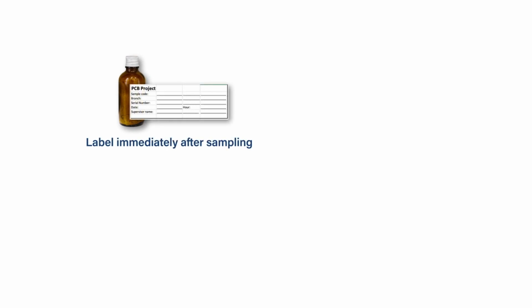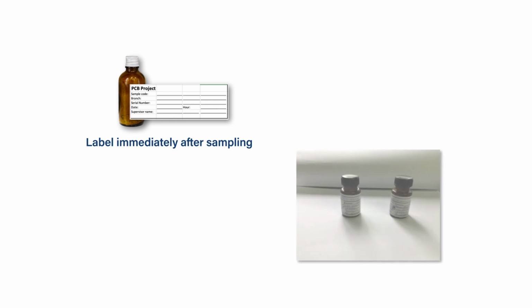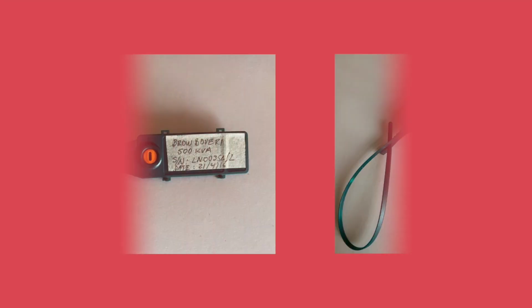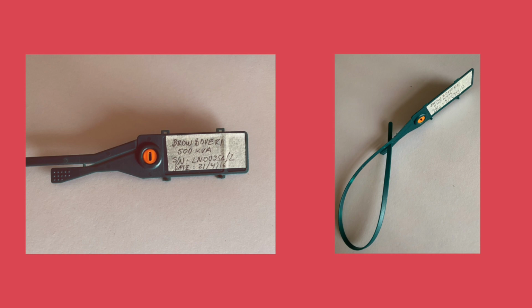The glass bottle containing the sample must be labeled immediately during sampling. The label should include a unique sample ID that allows the sample to be matched to the equipment from which it was taken. The information plate on the transformer may also be renewed, for example, with resistant plastic labels.